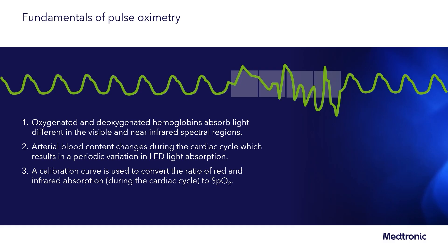We can break the fundamentals into three important parts. First, that oxygenated and deoxygenated hemoglobin absorb light differently. Two, as arterial blood content changes, so does the LED light absorption. Three, a calibration curve can be used to convert the ratio of red and infrared absorption to SpO2.